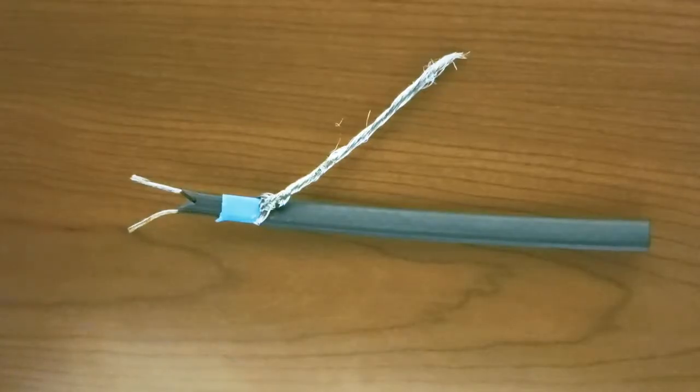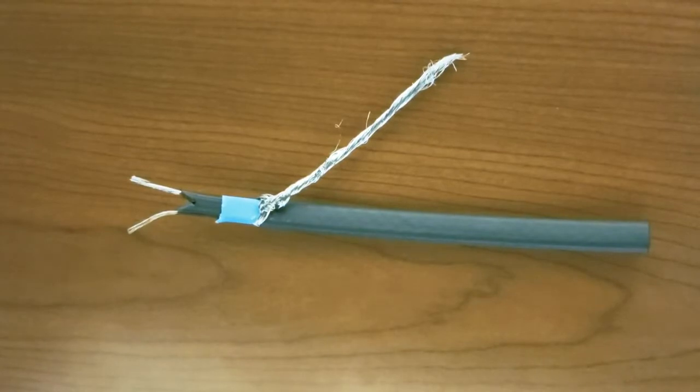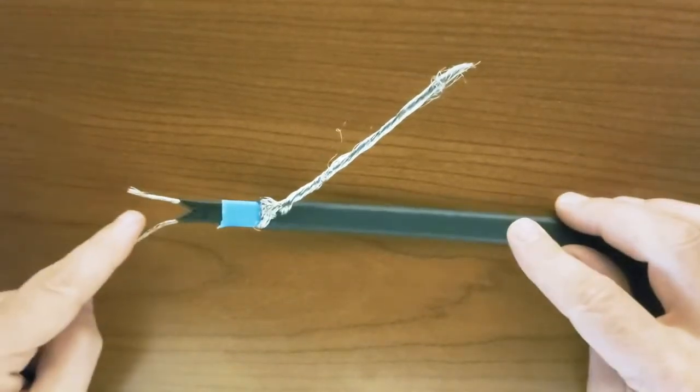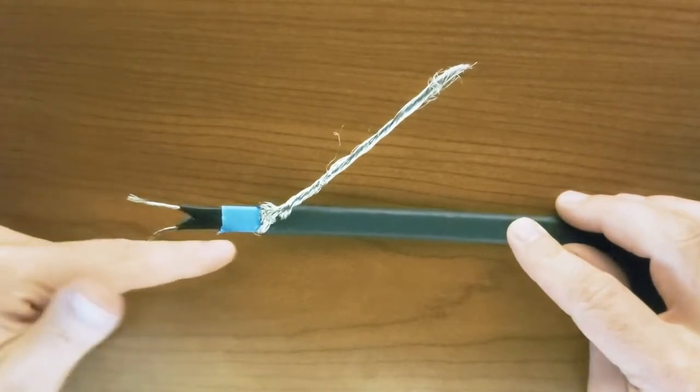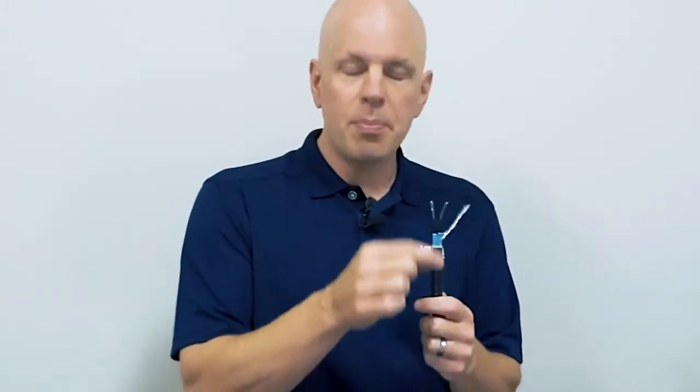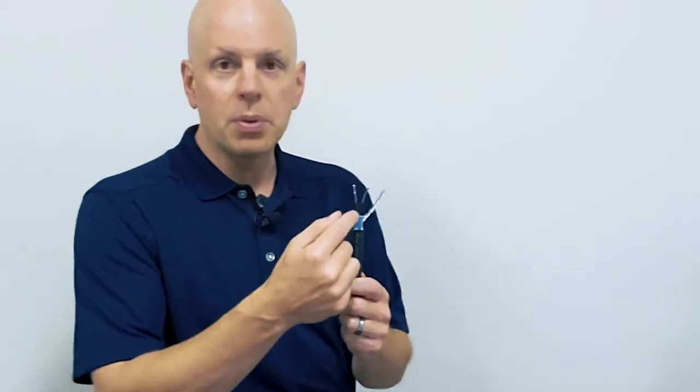Going back to heat trace, because it's a self-regulating product, you don't have that overlapping burnout issue that you do with heat tape. See these two parallel bus wires here and that black stuff in the middle? Well, that black stuff is called carbon black, and it's electrically conductive. That means that electricity flows up one wire, across the carbon black to the other one, and then down. So at any point along this cable, the circuit is complete. Now the carbon black will expand out at a point of crossing, regulating the flow of electricity and preventing a burnout.